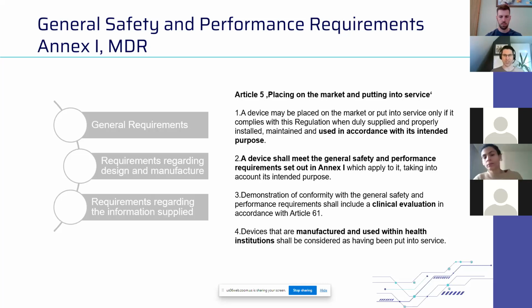Demonstration of the conformity with the GSPRs shall also include a clinical evaluation according to Article 61. Good. So next to checking the validation, next to checking the technological characteristics, you also need to provide proof points that your product is safe in clinical use and can also reach its clinical purpose and its clinical advantage. And whether it's to protect wounds from getting dirty and infected by using a plaster, or whether it's a computer tomography machine being used to create images that are suitable for diagnostic reading, where you can detect lung nodules, cancers, or I don't know, whatever, fractures, yeah? You need to be able to demonstrate that in real life. That means you need a clinical partner in most cases.